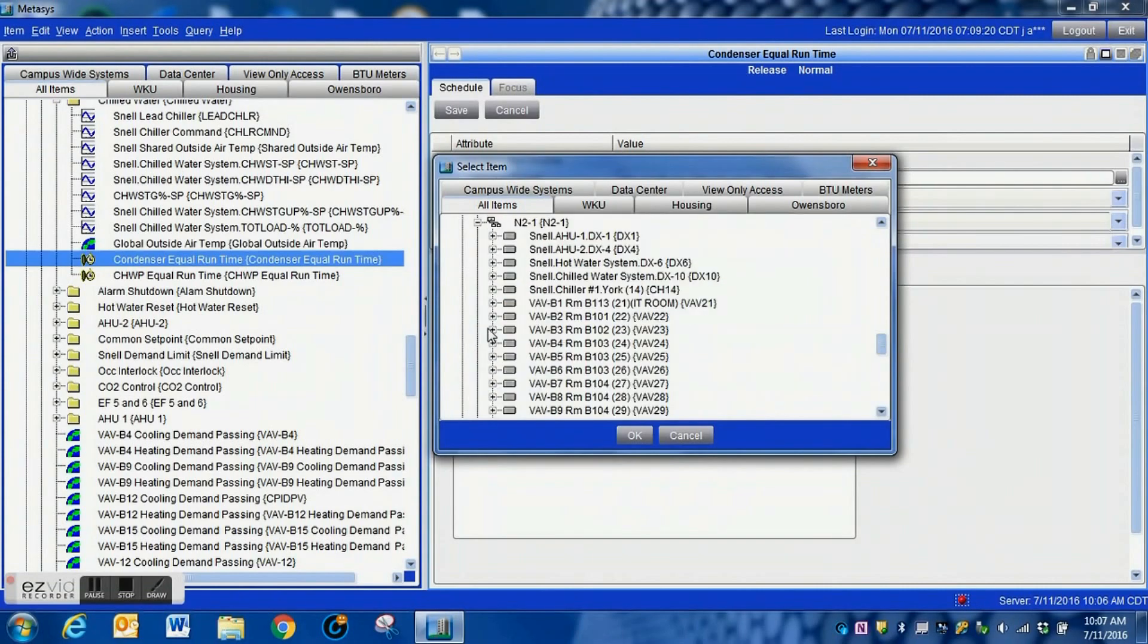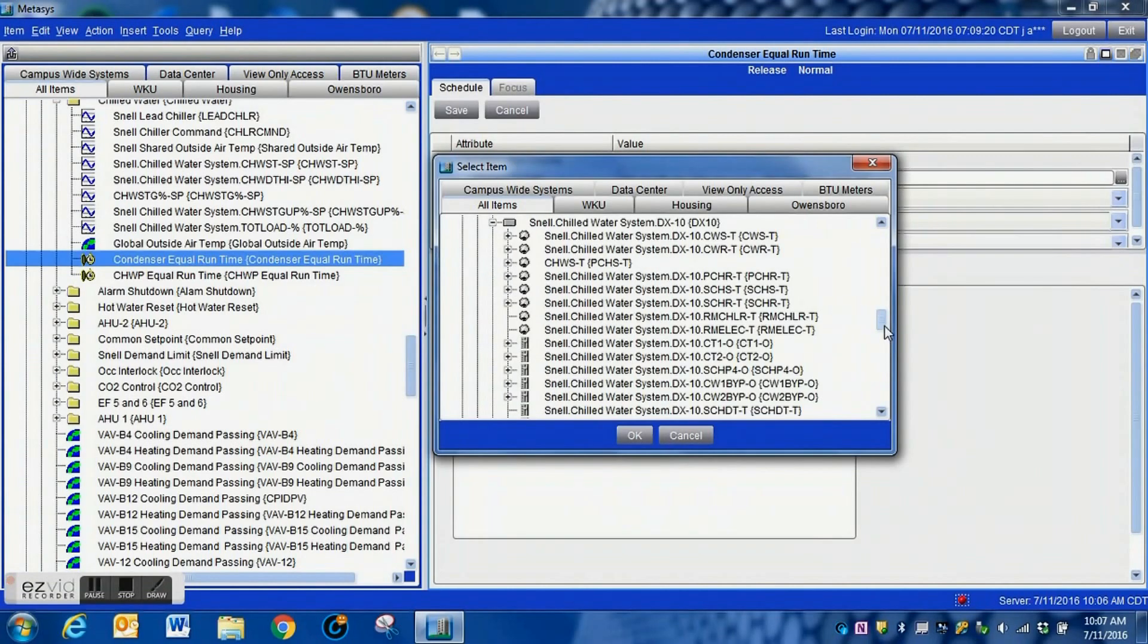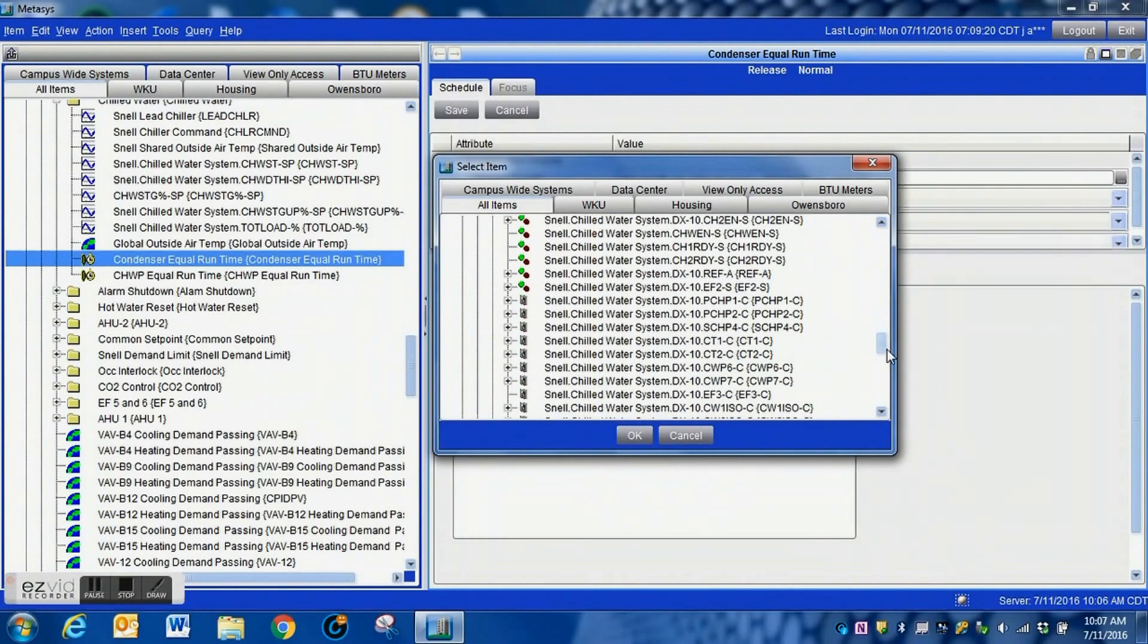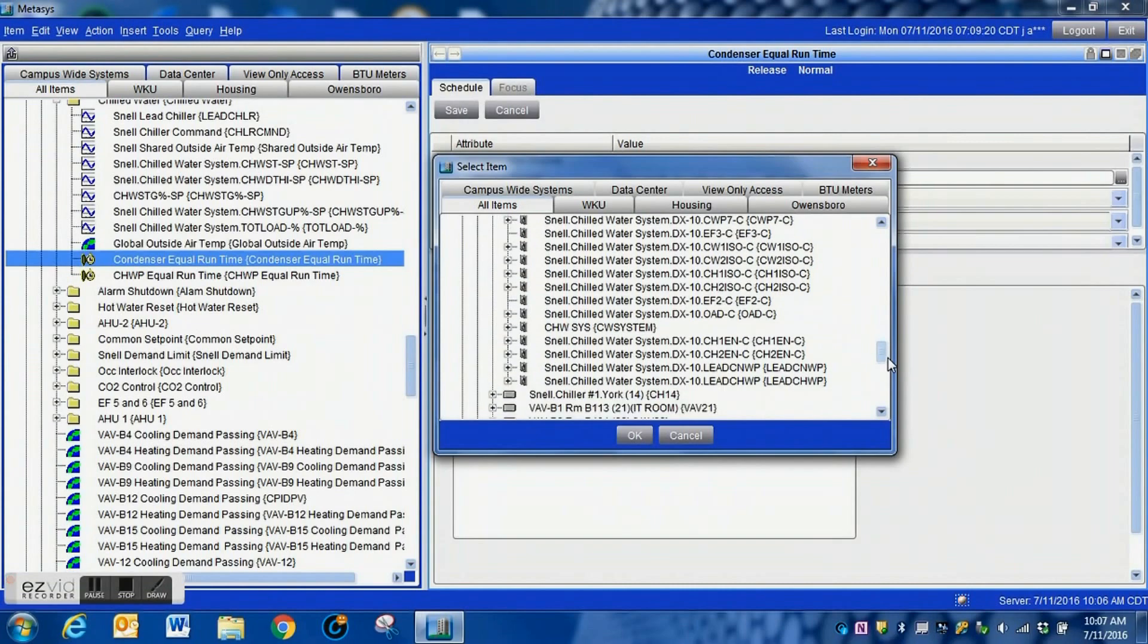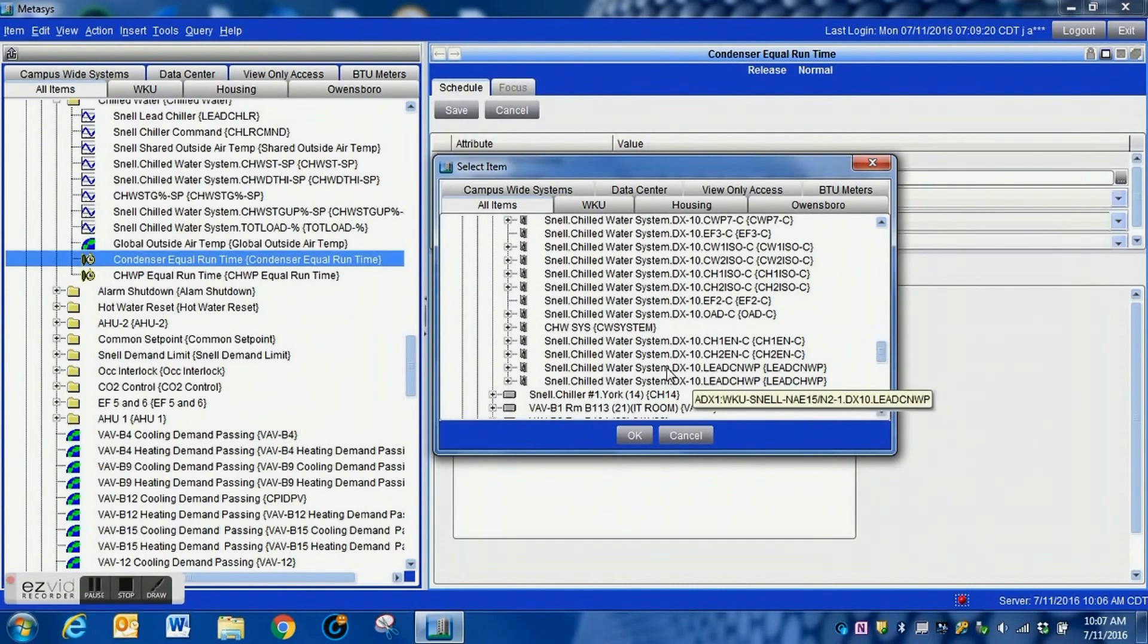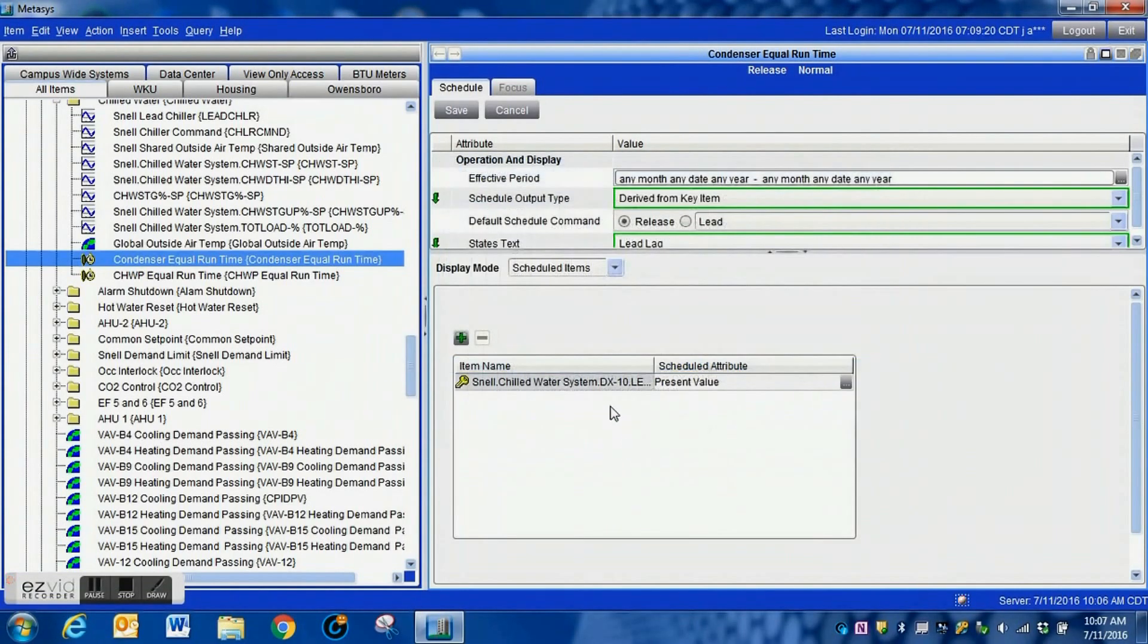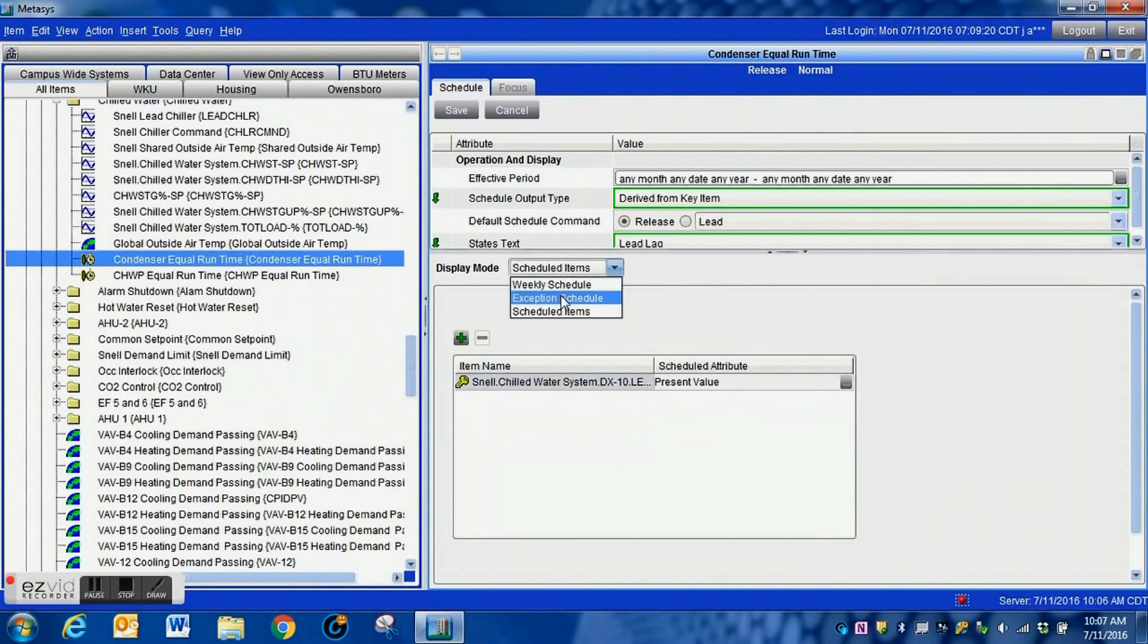I'm going to get the plus sign and then I'm going to drill down into my system and actually find that lead lag point within the chill water system and that's what we're going to bind this schedule to. So we just simply drill down, go into the particular controller, go all the way down to the point that you wish to link it to, and right here we are.